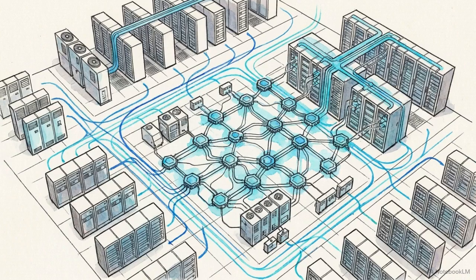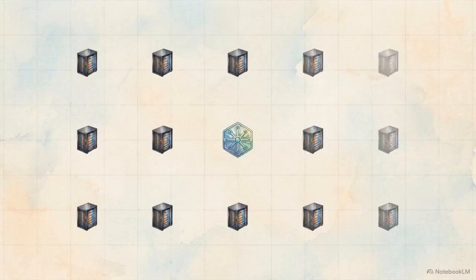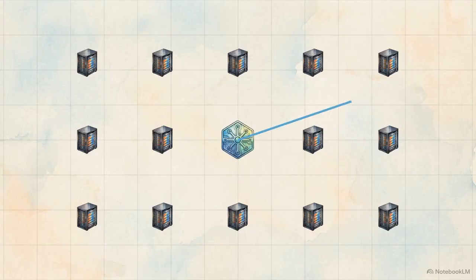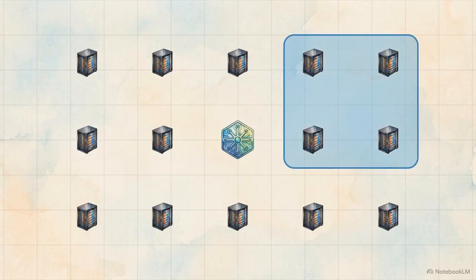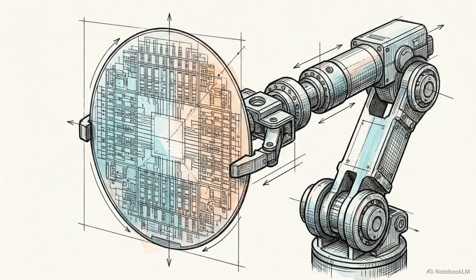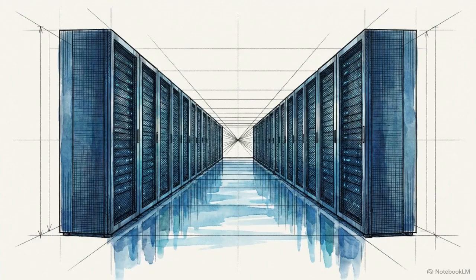Facilities now use AI-based cooling optimization to constantly analyze vast streams of historical and real-time environmental data across the entire data center. This map shows that AI operating in real time. It can predict incoming computational workloads, and instantly push extra cooling capacity to specific racks, preemptively icing the exact hardware zone moments before the data spike hits. The ultimate ceiling for global computing power is no longer determined by chip manufacturing speeds. The true limit is our ability to intelligently engineer away the heat left behind.